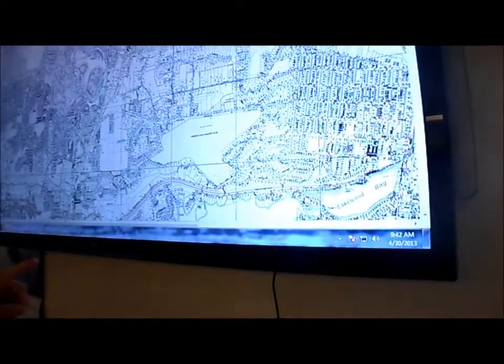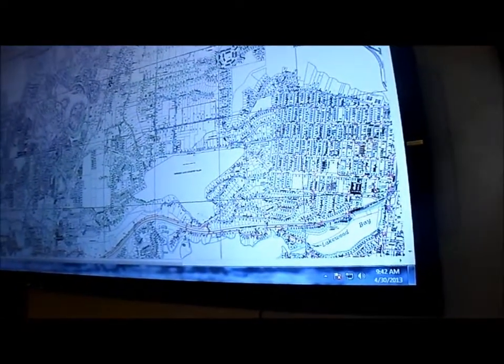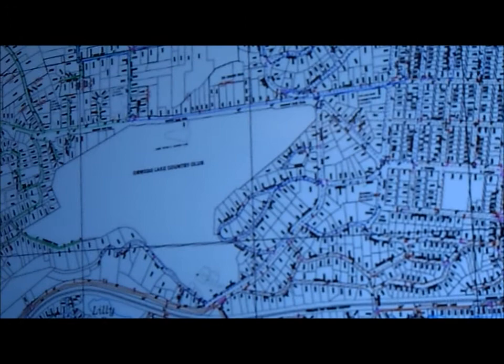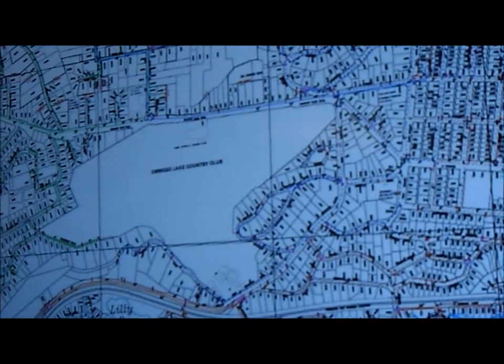Now, I don't see any contour lines on this map showing changing elevations. Right, we don't show that on here. But there is quite an elevation difference. The top of Nansen Summit here is just a couple feet shy of 1,000 feet, where lake level is 98 feet. Oh, wow. So that's a lot of drop. Our big issues are that change in water pressure, so we have a lot of regulating stations to compensate for that pressure drop.